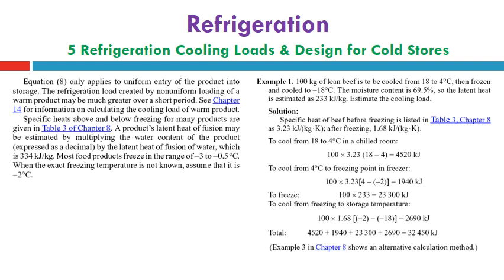About 100 kilogram of lean beef is to be cooled from 18 to 4 degrees Celsius, then frozen and cooled to -18 degrees Celsius. The moisture content can be considered as 69.5%. So the latent heat is estimated as 233 kilojoule per kilogram, which is the product of 69.5% by 334. If we take the product of these two values, we get a latent heat based on the moisture content of this lean beef to be frozen. Estimate the cooling load during this freezing.